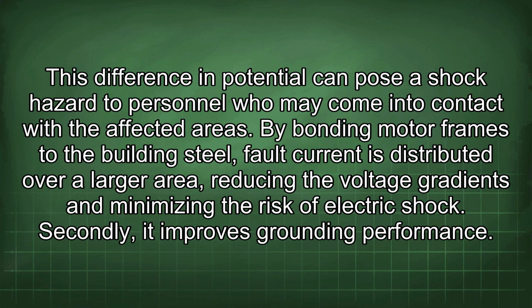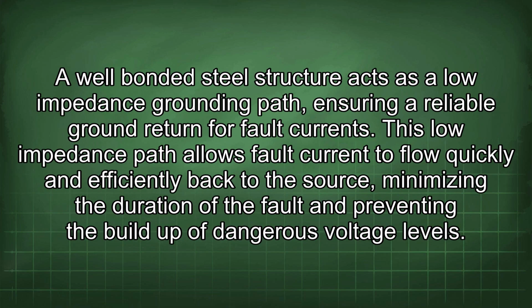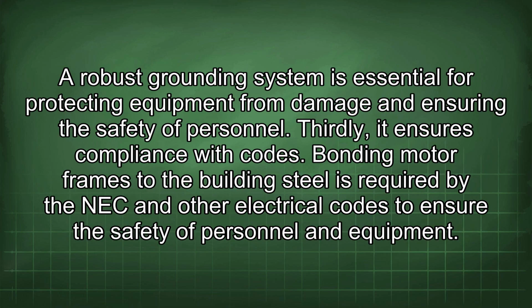Secondly, it improves grounding performance. A well-bonded steel structure acts as a low-impedance grounding path, ensuring a reliable ground return for fault currents. This low-impedance path allows fault current to flow quickly and efficiently back to the source, minimizing the duration of the fault and preventing the build-up of dangerous voltage levels. A robust grounding system is essential for protecting equipment from damage and ensuring the safety of personnel.